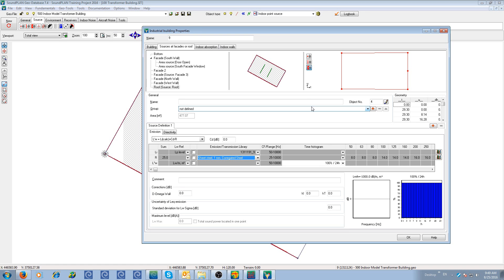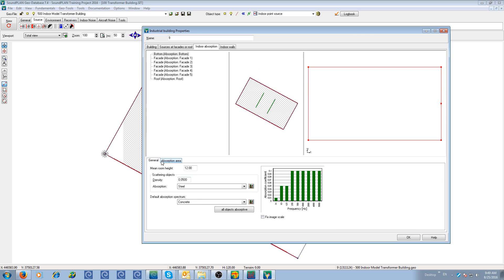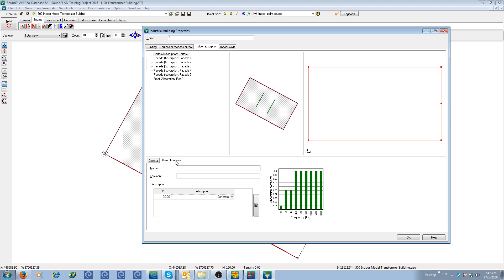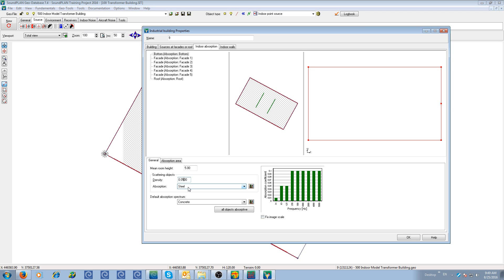For the interior noise modeling, we have to define the interior absorption. So here we have two tabs at the bottom, a general tab, and then all the absorption areas inside the room from the floor, the facades and the roof. On the general, we have the average room height, in this case five meters, the density of scattering objects, and the absorption of the scattering objects. This parameter is not really that critical for small rooms, mostly affects the propagation in large scale warehouses. Additional scattering objects, shelving tables, any kind of objects inside the building adds additional mitigation on the propagation.